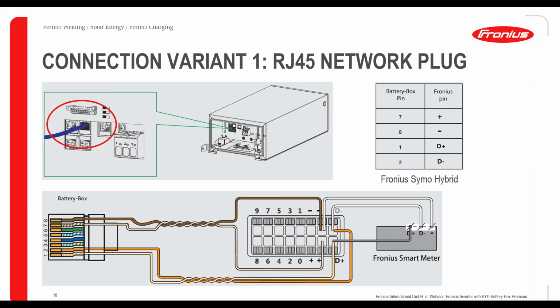The other 2 cables are the plus, so this 12 volt plus signal, and the ground connection. And these 2 cables should again be twisted to each other. So this is in this case the brown and the white cable that you see here. Furthermore, for connection to the Fronius smart meter, it is important to connect the D+, D-, and ground connection from the data manager plug to the Fronius smart meter. So this is then the third connection to the Fronius smart meter for visualization and tracking of the PV surplus energy in the system.